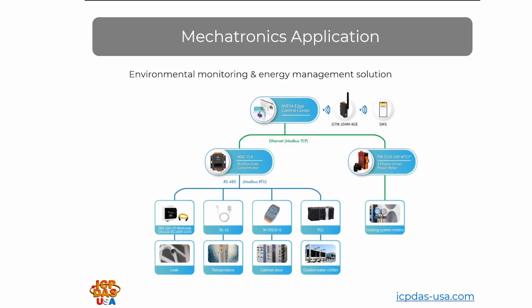And this MDC-714 Modbus data concentrator is connected over Ethernet to the Windows-based computer running Aveva SCADA software. And then over the RS485 bus, the Modbus data concentrator is connected to different equipment. The DL10 is taking temperature measurements over Modbus RTU. And then there's also the ISN-104 leak detection module and the cable. Those sense if there's a leak, and they sense liquid, and then it passes the data back to the Modbus data concentrator, which collects all the Modbus data in one place.